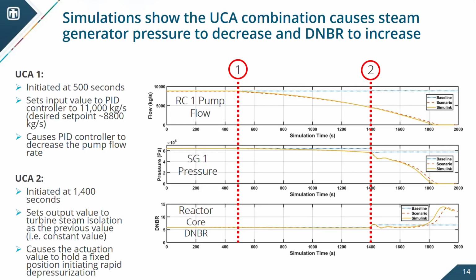Well, the DNBR basically represents when a steam jacket forms across the fuel and prevents the liquid water from coming into contact. So you're no longer able to conduct heat and transfer it from the fuel rods to that. Now, when the DNBR is flat, like you're seeing before those two UCAs, there's no rate of change, you do not have that steam jacket forming. You do not have the fuel being insulated by those steam jackets.